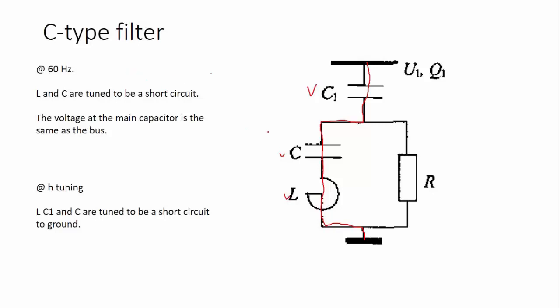At fundamental frequency, L and C is a short circuit, so the only thing operating in the filter is C1. At the tuning frequency, the whole filter is a short circuit, so that harmonic is filtered. Now, because it's a parallel circuit, you will have some current going through the resistance, of course, but most of the current will go through this branch because it's a short circuit. At 60 Hertz, the reactive power will flow mainly through here. Some will go through here, yes, but mainly through here. And at the tuning frequency, this whole thing is a short circuit.